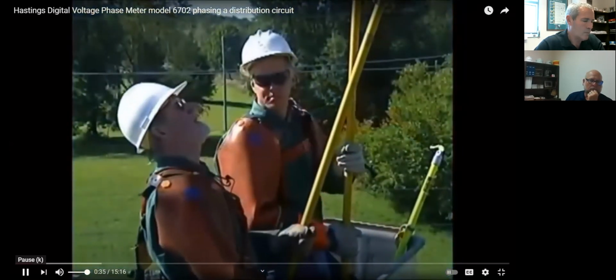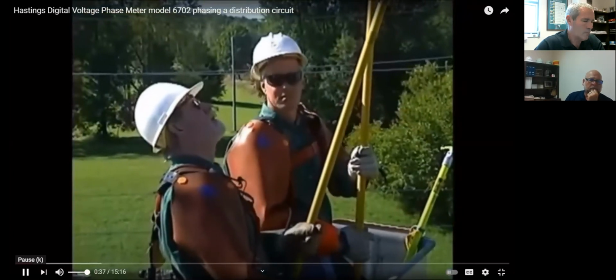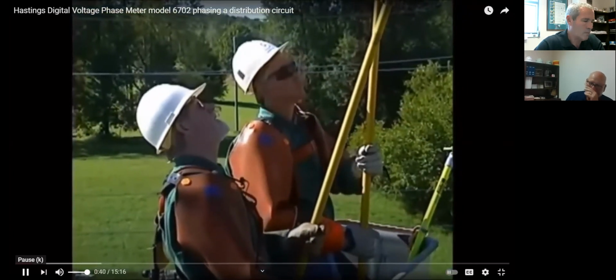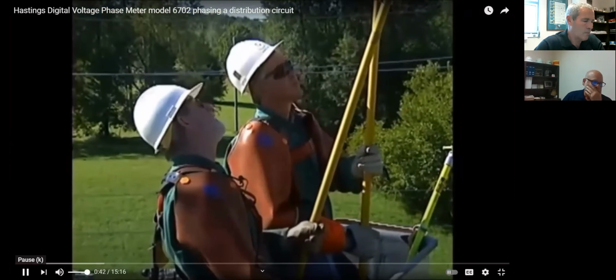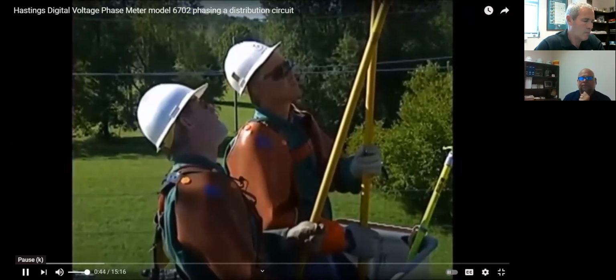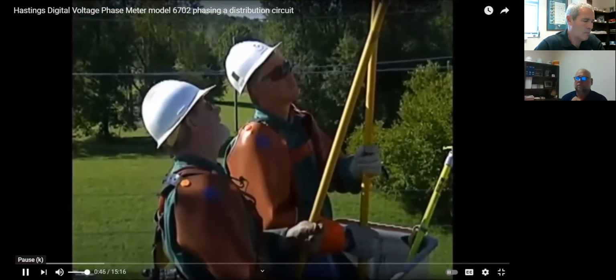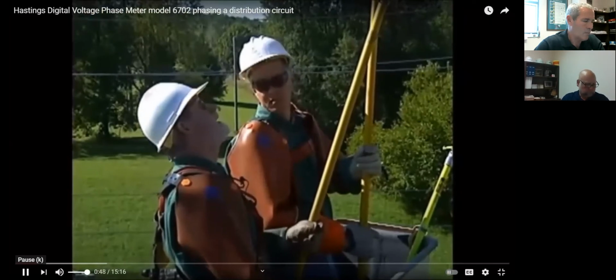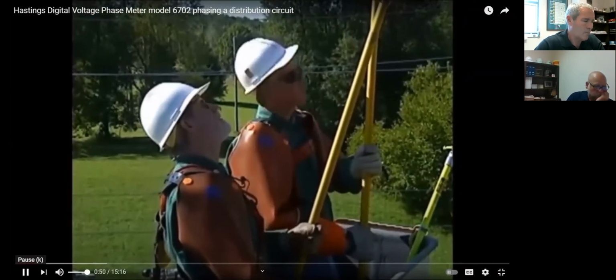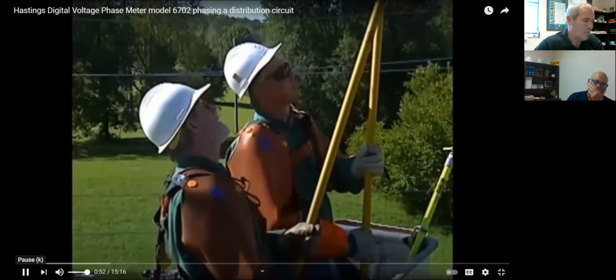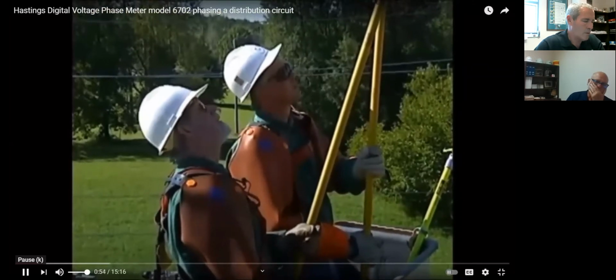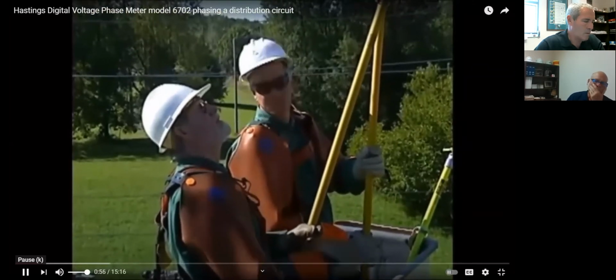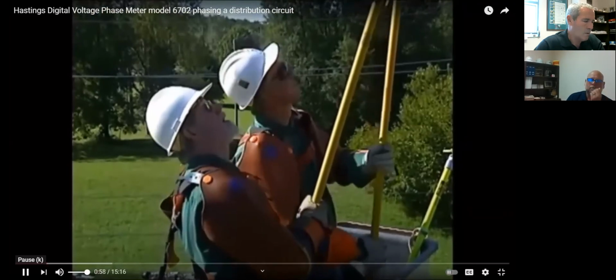Well Kirk, if you're ready, let's make sure that we have voltage on both sides of these open switches. We'll go road phase to center phase, road phase to field phase, and then center phase to road phase, and center phase to field phase. Then we'll do the same thing on the bottom side of that cutout. We'll have this phasing procedure completed, and we can close this feeder together.